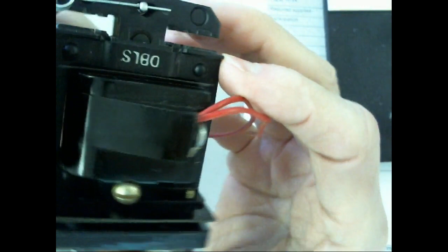And also they have what we refer to as a shading coil on AC right here. What this does is it prevents the relay from vibrating, because AC goes to 0, 120 times a second. When there's 0, there's no current flow through the coil. If there's no current flow through the coil, this thing would have a tendency to drop out like this, but before it got out anyway at all, it would put it back in. So if we didn't do something, these AC relays would literally chatter - they'll go bzzz, real loud.